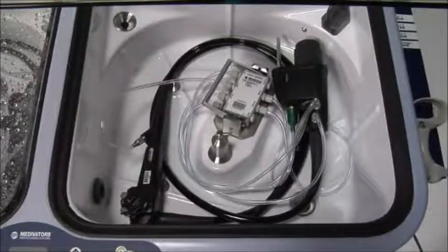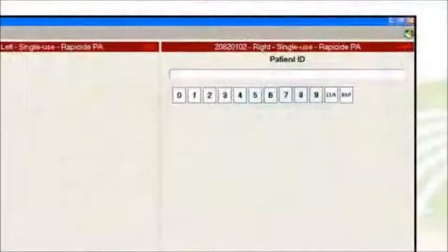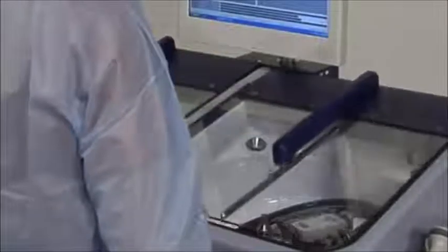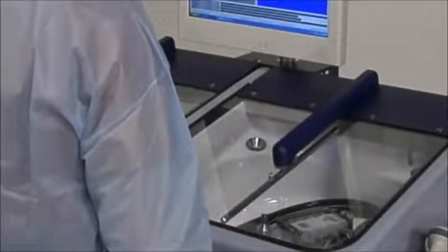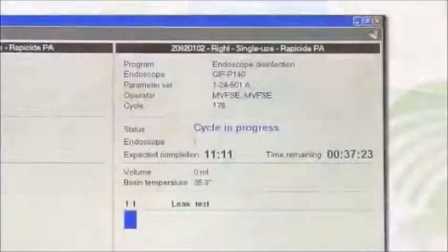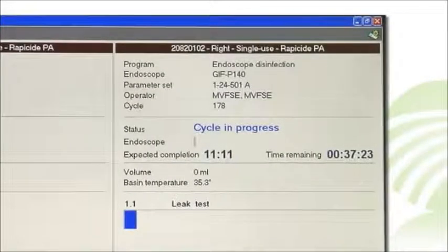Depending on the software version of your unit, you may also be asked to scan the barcode on the hookup connector block. You may then be prompted to enter the patient code and the physician code. You may use the barcode scanner or touchpad to enter this information. The lid will close automatically, and the disinfection process will begin. The program screen opens to allow you to follow the progress of the disinfection process.